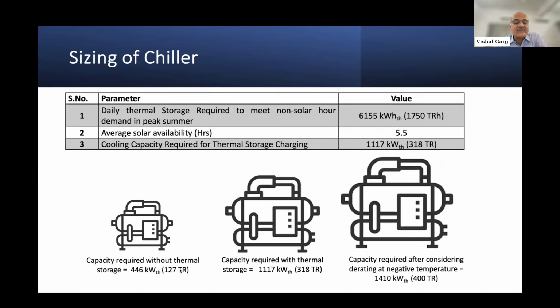We need a 127 ton chiller. But when we go for utilizing the energy available in the daytime for 5.5 hours, and we have to charge 1750 ton hours, then the chiller requirement becomes 318 tons, because this chiller should run only for 5.5 hours and generate the 1750 ton hours that is required in the night time. So we can see that the chiller is of 127, it becomes 318.